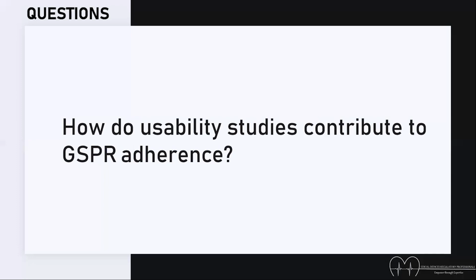And so we talked about one of the usability studies already that is required, and that is if you have laypersons utilizing the devices. And that's GSPR 22, where you would have to do a specific usability study on laypersons, understanding the skills and language requirements that these laypersons have. The second part where we find reference to the usability studies is in the earlier sections of the GSPRs, which is on the risk management versus the clinical benefit. And so especially if you focus on GSPR 5, that focuses on the use error. So you can look at it in a broader perspective.